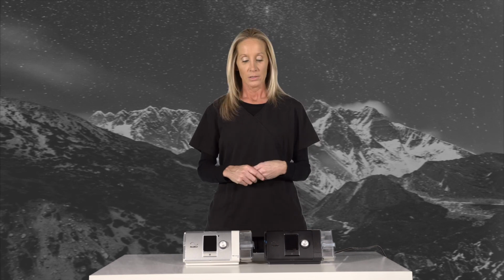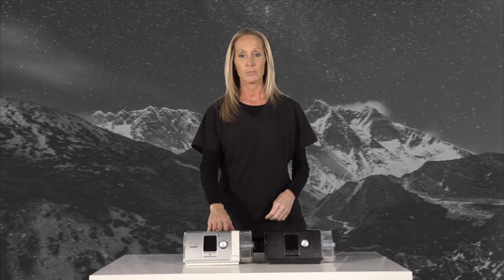Another indication might be that you're at a really high pressure. On high pressures, sometimes people do better on a bi-level device. Bi-level devices use two different pressures, one higher pressure on inhalation and a lower pressure on exhalation. So that mimics natural breathing, and the body generally does better with bi-level devices whenever you're having trouble with that back pressure with CPAP. Now you have a better understanding of the difference between a CPAP device and a bi-level device.